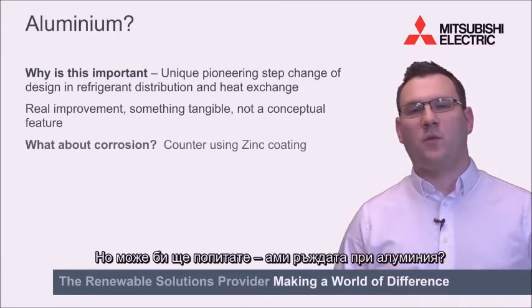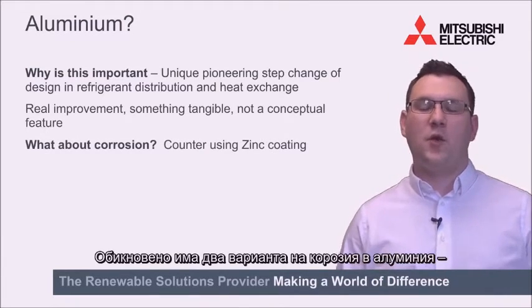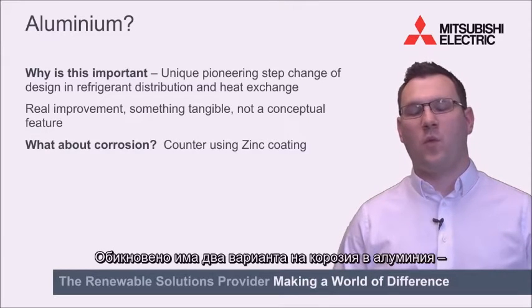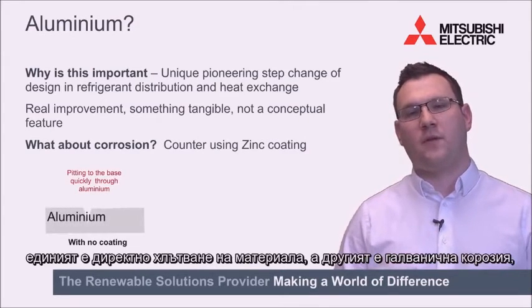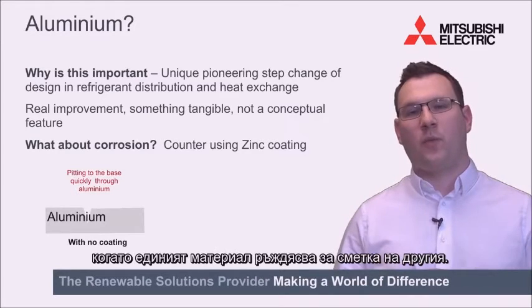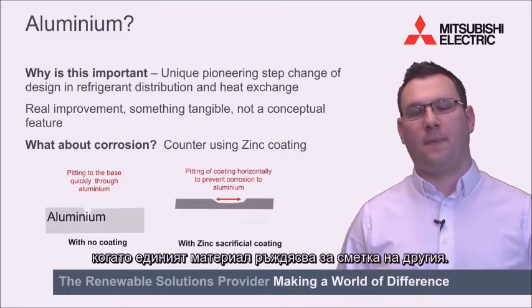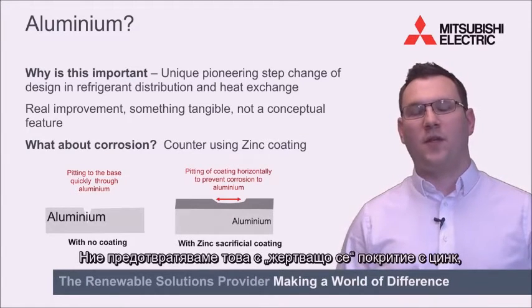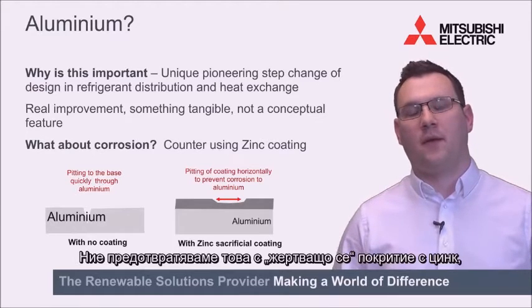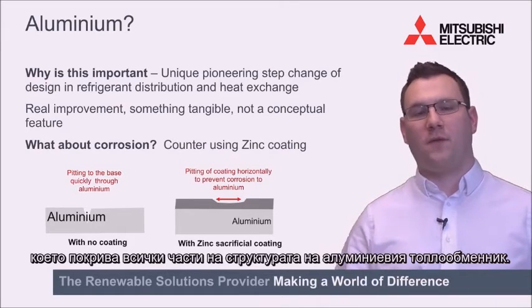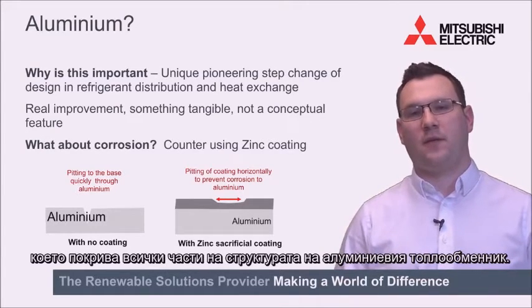But I might hear you ask, what about aluminium and corrosion? You typically get two variants of corrosion in aluminium. One is pitting directly through the material, and galvanic corrosion where one preferentially corrodes towards the other. We overcome this with a sacrificial zinc coating, which covers all parts of the aluminium heat exchanger structure.